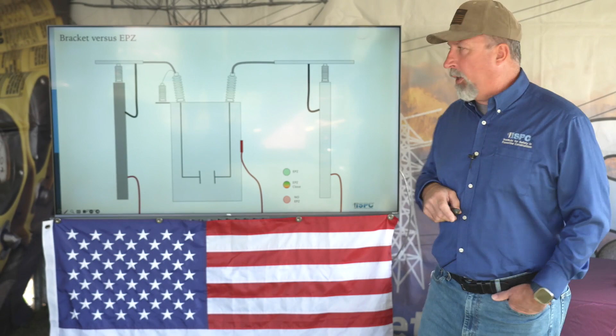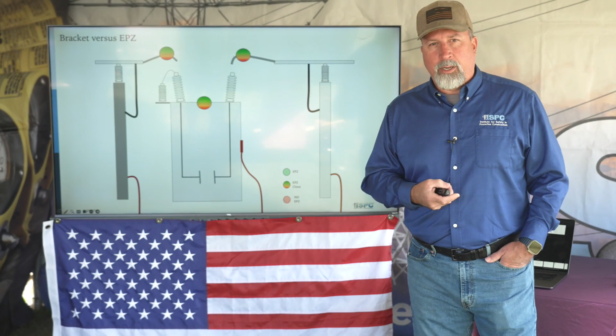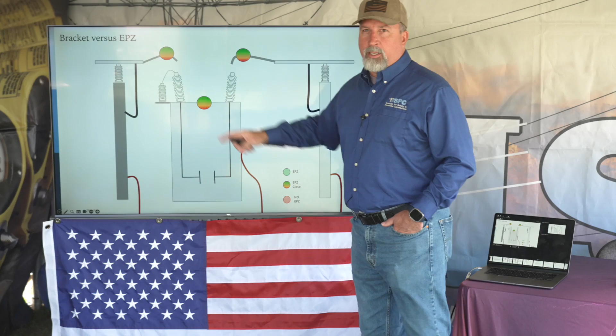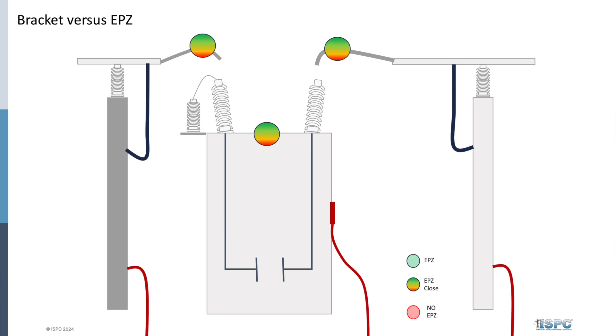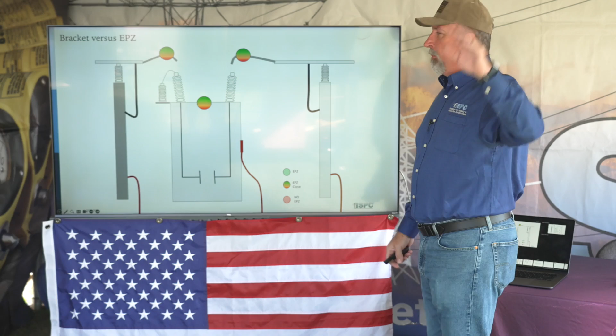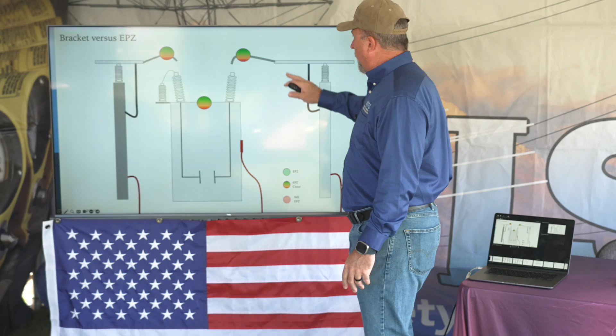But should you be disconnecting this circuit breaker, say for removal or replacement, as soon as you take the leads off the breaker, now you've just created some differences of potential. So it's understanding that there's a potential there for a hazard. I'll be the first to admit I've done this 100 times, because I didn't know any better, or I didn't think about it, or recognize that, hey, by unhooking these leads to the breaker, I just created a difference of potential.